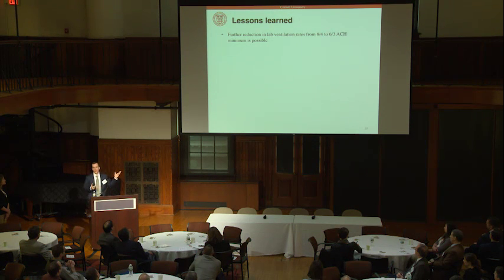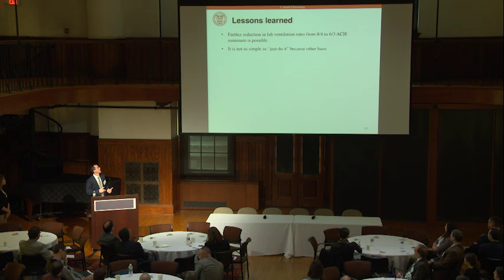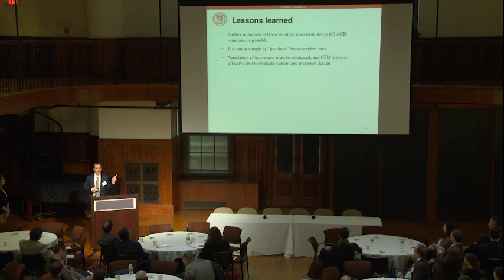So what did we learn? We learned that it's possible to reduce air change rates from 8 and 4 air changes down to 6 and 3 air changes. That's possible, just not as simple as going out and doing it -- you have to do some analysis and make sure you're looking at how the air is actually going to flow through the labs. This was pretty important.